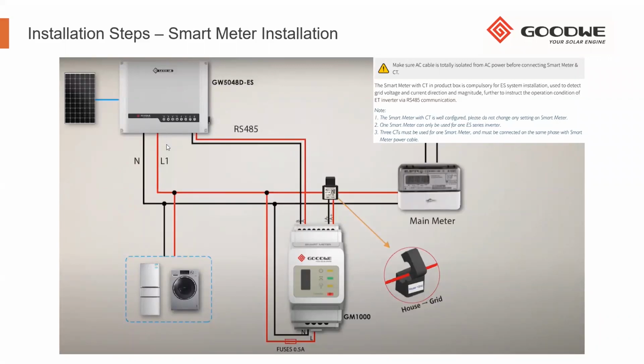The inverter comes with the cable to the meter. It is 10 meters, but that can be extended to 100 meters should the main DB board be quite a bit further away. I know some customers just install this in their incoming board to the inverter if it's far away from the DB, but then you really do not get the best out of your system if that's not reading the entire house load.